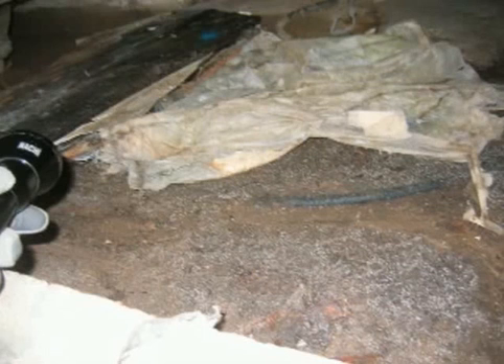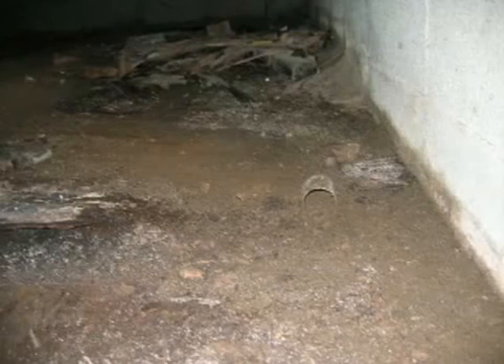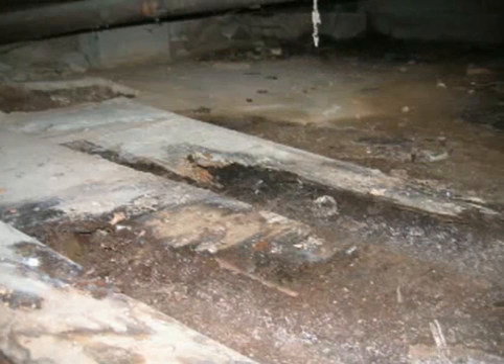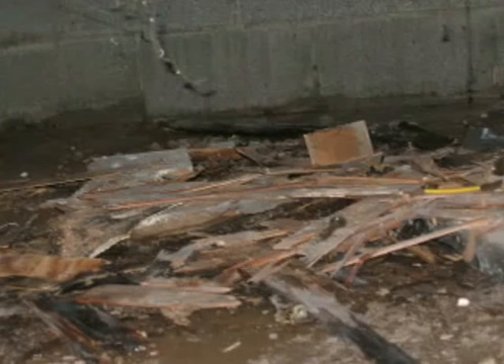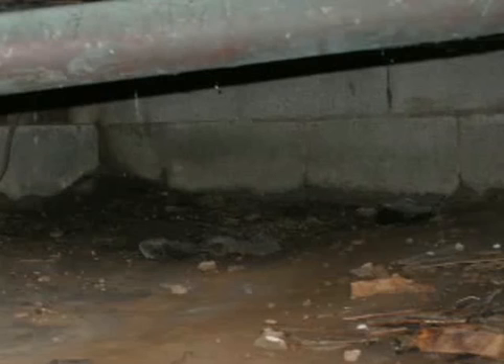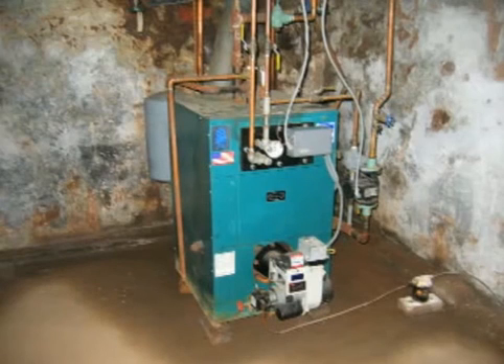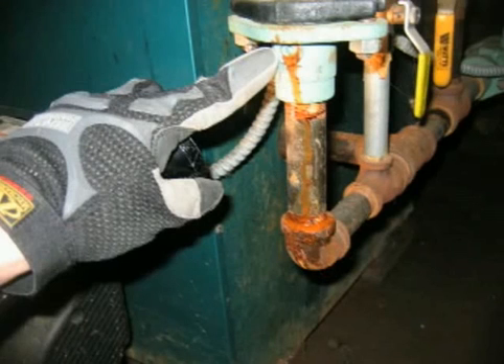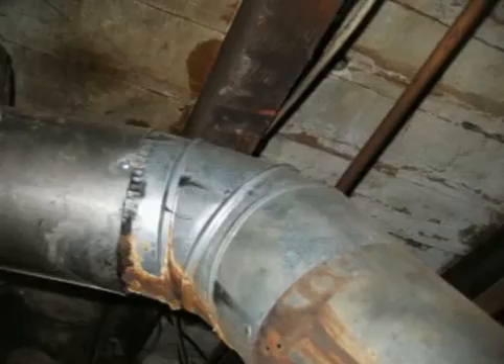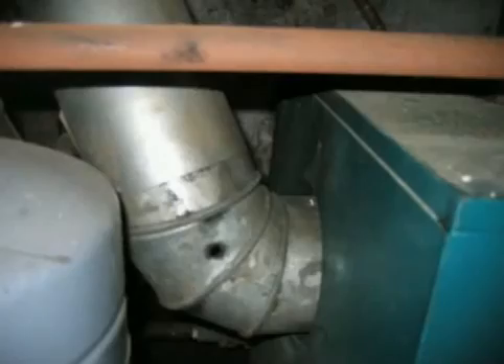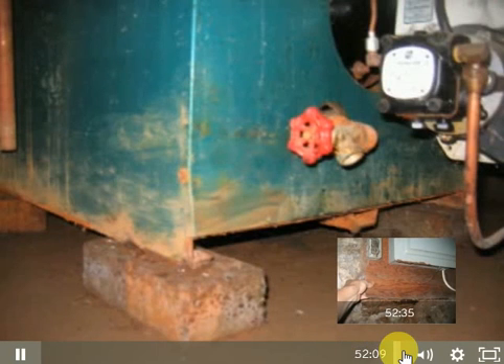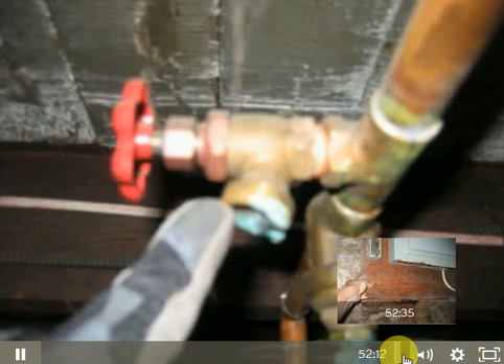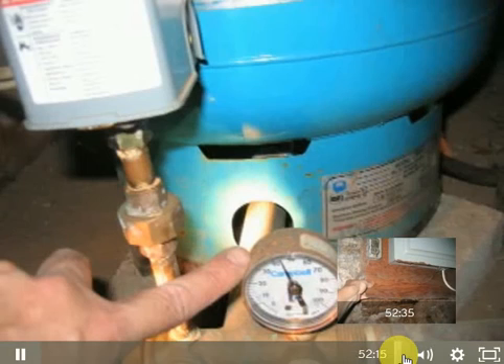Places flooded in the past. There's debris and building materials lying on the floor, which is food for mold. You have moisture, you have good temperature, and you have food. Around the boiler system, there's a lot of water. The boiler itself is leaking. That needs to be reported. The flue pipe has moisture coming down the chimney stack. That's moisture intrusion coming from the chimney stack. The jacket of the boiler shows a history of water problems. There's an active drip coming from the boiler valve.